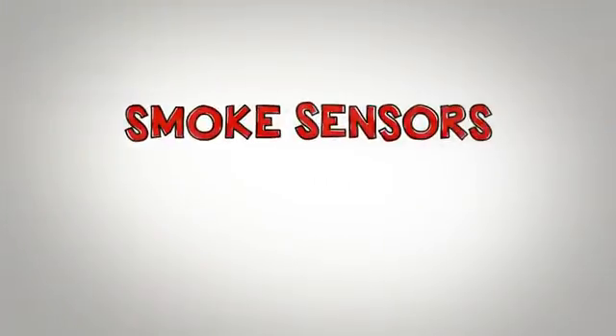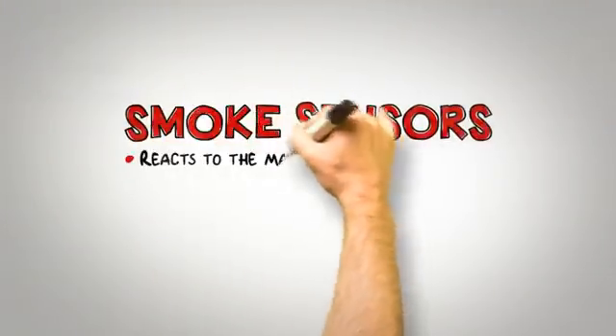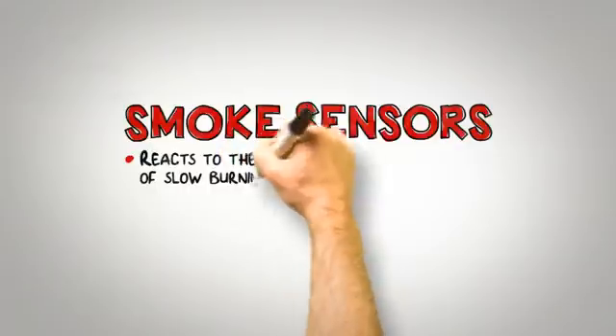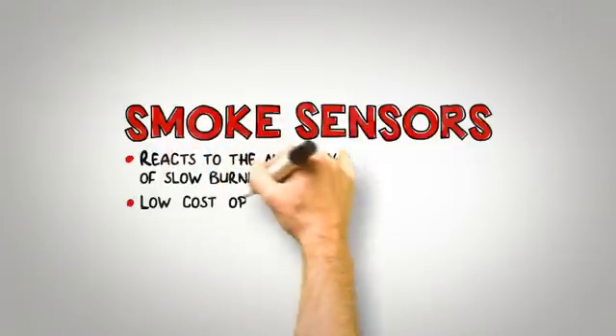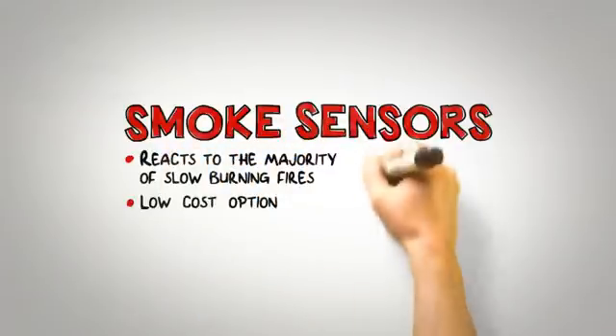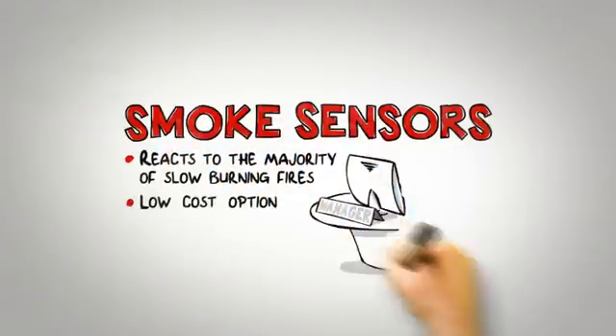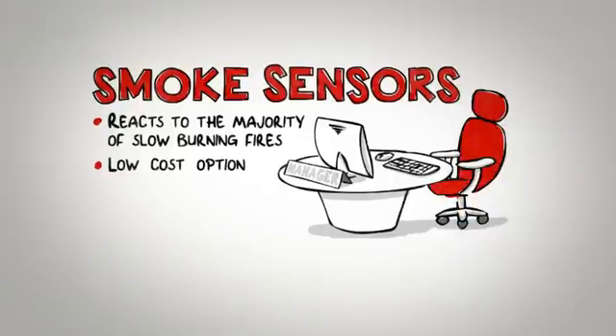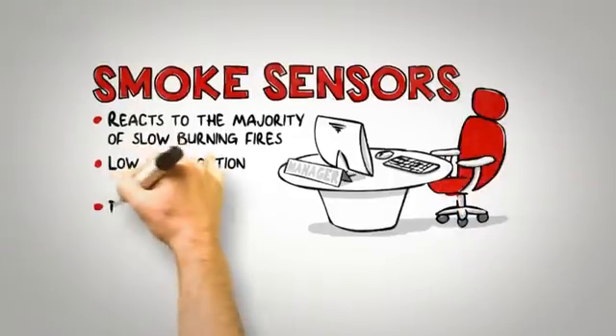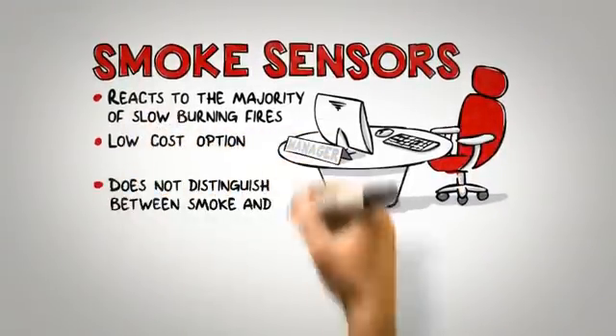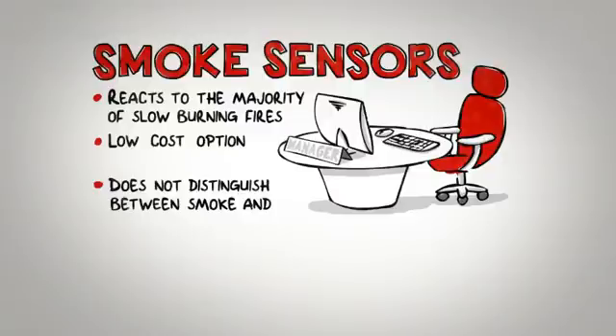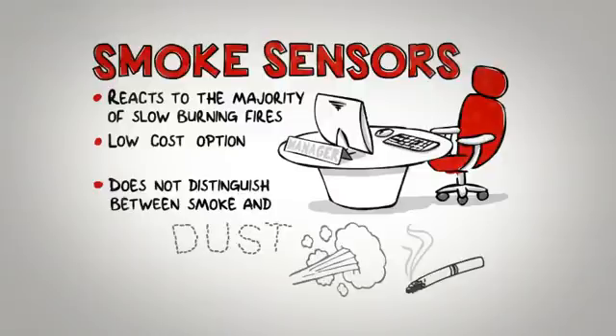Smoke sensors. For many buildings, the optical smoke sensor is the preferred choice. This device reacts to the majority of slow burning fires and is a low cost option. The detector is suitable for clean environments such as an office area. However, it does not distinguish between smoke and many of the common causes of false alarms such as dust, steam, cigarette smoke and cooking fumes.